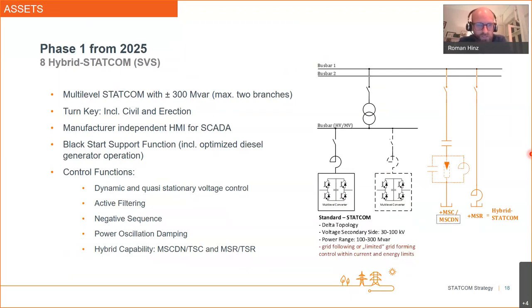This was the reason why in this current tender for the eight STATCOMs, which we're tendering right now, the grid forming behavior is more like optional. But for example, if somebody has this kind of behavior, they will get better evaluation points for that. But anyhow, we have to be realistic. This grid forming behavior right now is maybe not applicable, but in the future it will be, because we spoke with the manufacturers, and so far as we know, most of the manufacturers have put a lot of budget into their R&D departments, and they're developing this grid forming behavior with regards to control and also with regards to this additional energy storage system. But so far, we're tendering today, and we already started this in the beginning of this year.